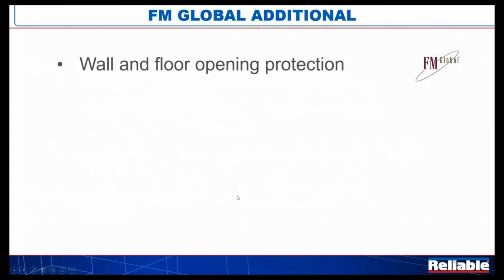So that was all a lot of NFPA 15 stuff. Again, most of that is replicated in Factory Mutual 4-1N. But Factory Mutual has some interesting stuff, and I hate to say it's a little bit of a hodgepodge, but I just went through and pulled in some additional stuff out of 4-1N. 4-1N allows water spray systems to be used for wall and floor opening protection. So maybe you've got a 2-hour wall between areas of a building, but you've got a conveyor running through it, or whatever it is. FM allows you to look at that and gives us some guidelines on how to protect those openings between floors and walls within the confines of what we're talking about today.